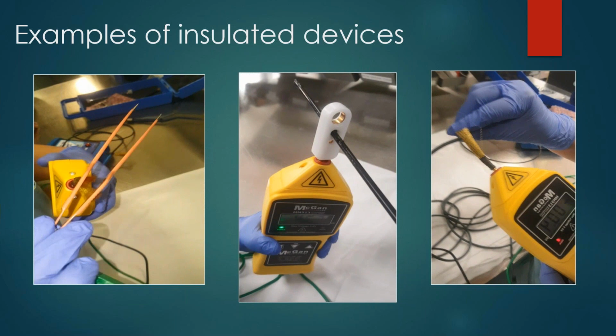The first video was a forceps. In this particular case, the forceps looked fine. There was nothing wrong with it visually. But when you tested it, it actually failed 2 different times. In this particular facility, they weren't testing the forceps at all. The focus has always been on laparoscopic at this facility.